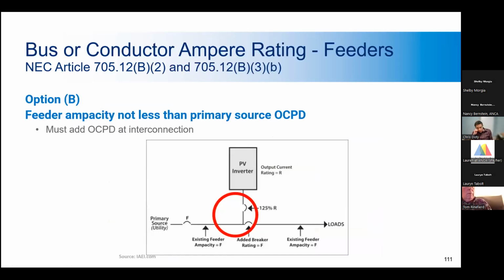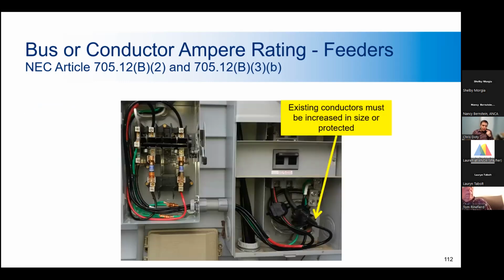Feeder taps are a type of interconnection that requires special consideration, sort of a hybrid load side connection. They have the potential to add additional available current to conductors and bus bars, and we need to consider this. In this case, in order to protect the conductors from the additional PV current, an additional overcurrent protection device has to be installed. This is covered in Article 705 in the code.